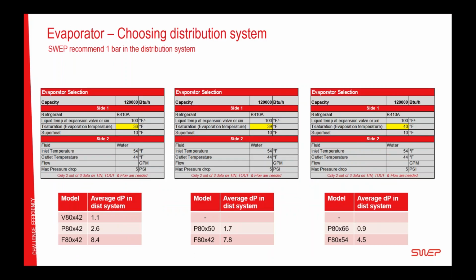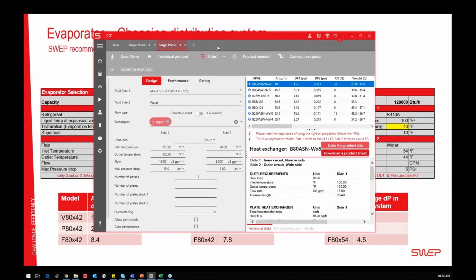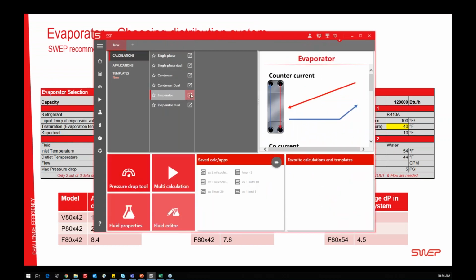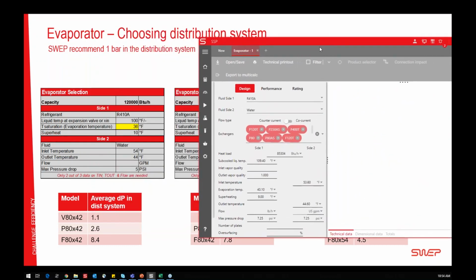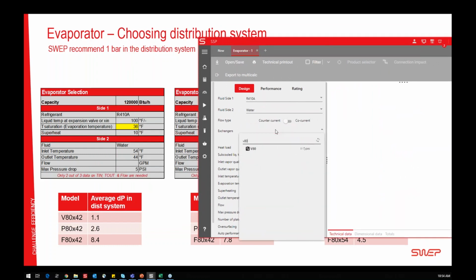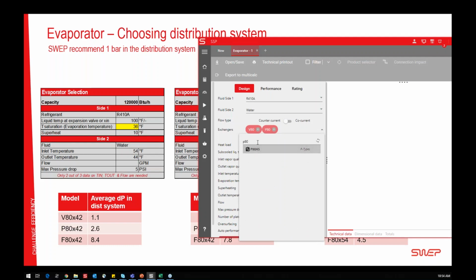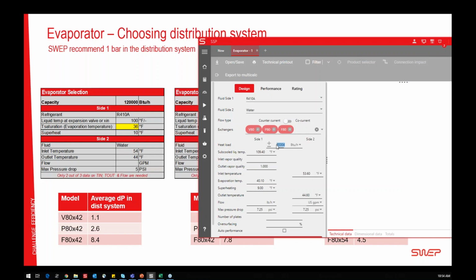Jolly good. Let's do the evaporator. I will close this down, and I will go to an evaporator and do it like this from scratch. Since I want a V80, I want a P80, and I want an F80. They are the same heat exchanger. The only difference is 3 different distribution systems. I have 10 ton, 120. I can change this down to US ton, 10 tons. The temperature of the hot side of the expansion valve is 100, meaning the temperature out from the condenser, including subcooling and everything. We have a target evaporation temperature of 36 and a superheat of 10. And the pressure drop on that side is actually not used normally.